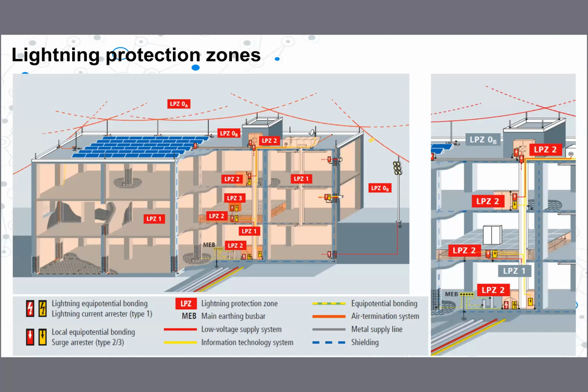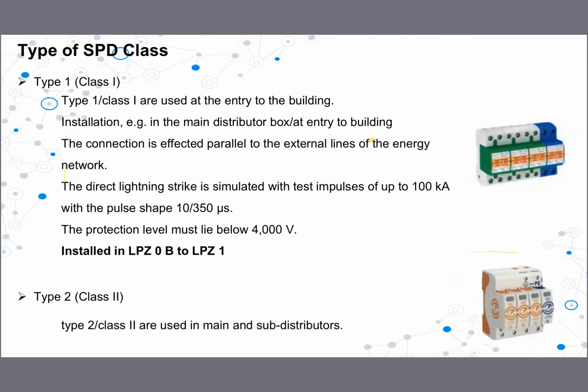So now, I explained before, we have 3 types of surge protection devices: class 1 or type 1, type 2 or class 2, and type 3 or class 3. Then let's try to understand a few special characteristics of these different types of surge protection devices, right? Type 1 surge protection devices are mostly used at the entry of the building. So that means we use class 1 in the main distribution board, right? We have the main distribution board at the entry of the building, right? So this device we use to protect against the direct lightning strike.